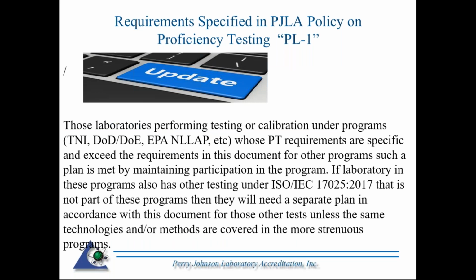So here's one of the updates here that we've added, and it may or may not apply to you, but these are for the DoD, Department of Defense, EPA, if you can see all the programs listed there. What's been added is that if you're performing testing or calibration under these programs, whose proficiency testing requirements are specific and exceed the requirements of this document, being PL1, for other programs, such a plan is met by maintaining participation in the program. If the laboratory in these programs also has other testing under 17025-2017 that's not part of these programs, they'll need a separate plan in accordance with this document for those other tests, unless the same technologies and or methods are covered in the more strenuous program. So this is specific to these programs.